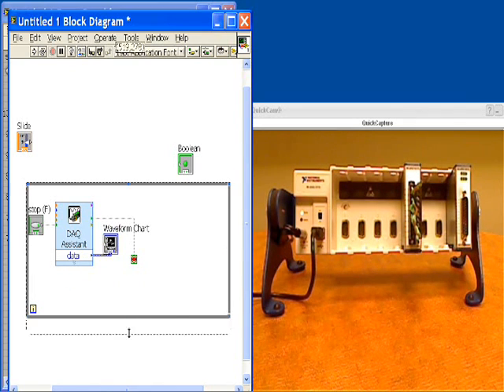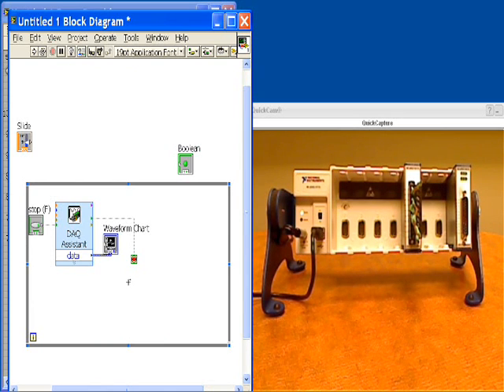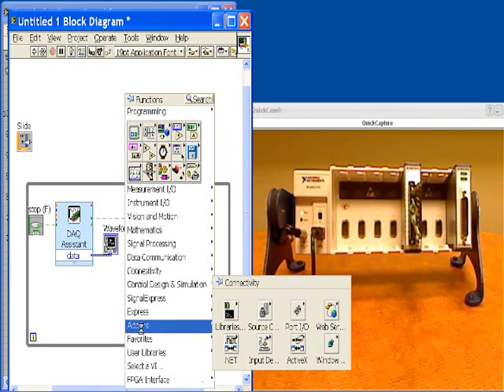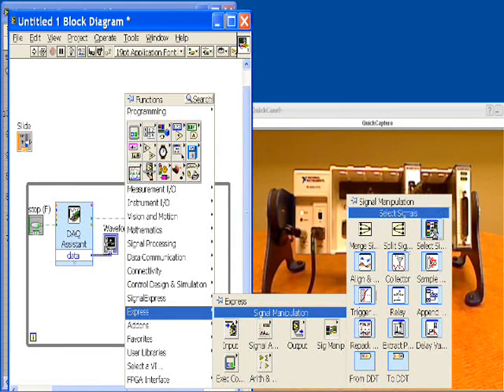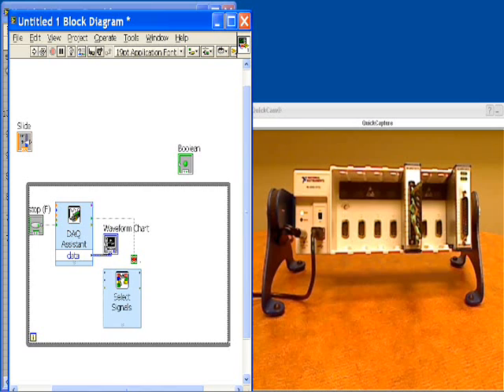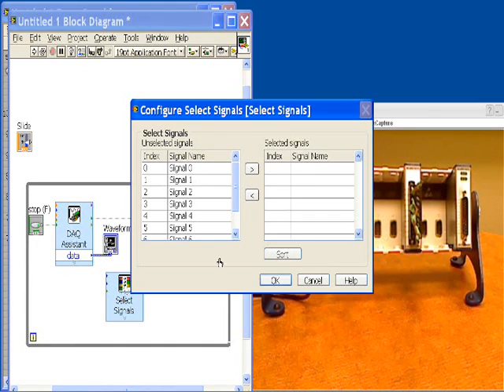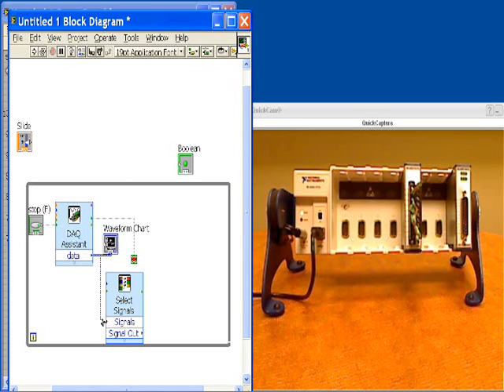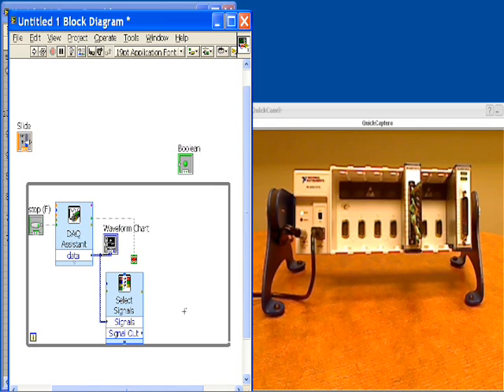Now we should be able to see data on our chart. For the alarming portion, we're going to alarm off of just one of the channels. To do that, I'm going to go to the express palette, signal manipulation, and select signals. By placing that on the block diagram and wiring in my data, I'm going to select signal zero and say OK. Now I can branch off of my thermocouple wire, run that into signals, and the output should be channel zero, the one channel that we've selected.